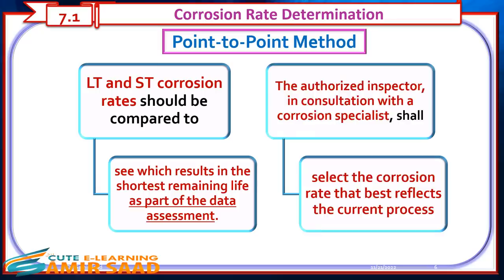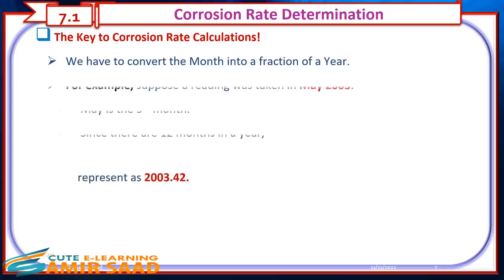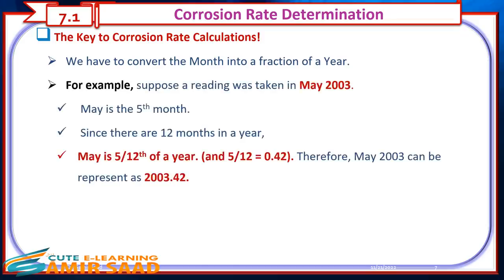The authorized inspector, in consultation with a corrosion specialist, shall select the corrosion rate that best reflects the current process. A key note on corrosion rate calculations: we must convert months into a fraction of a year. For example, a reading taken in May 2003 — May is the fifth month, so five-twelfths of a year equals 0.42. Therefore, May 2003 is represented as 2003.42.